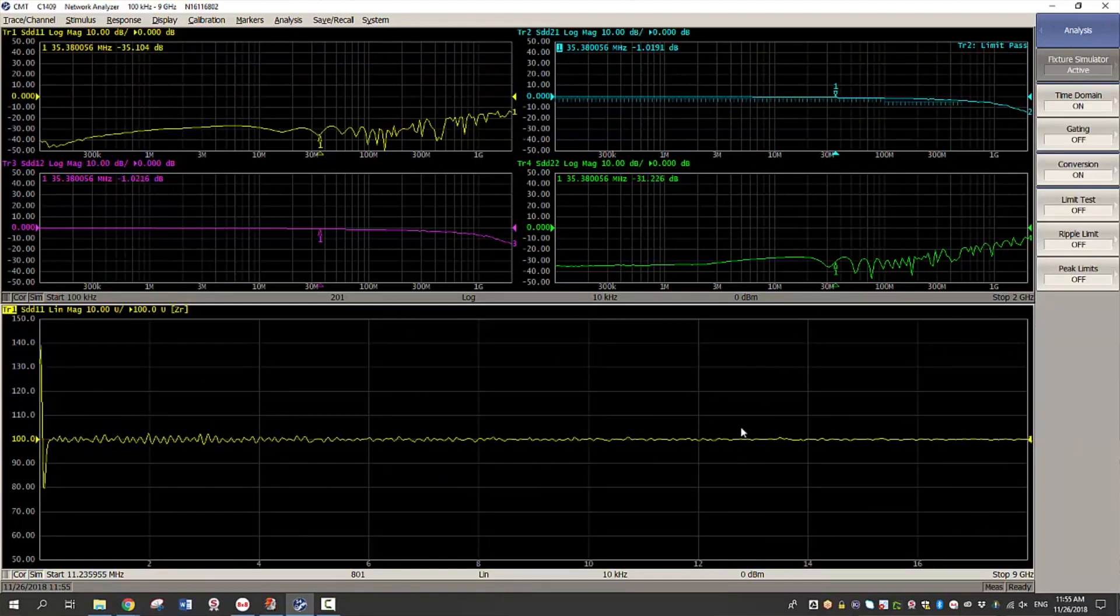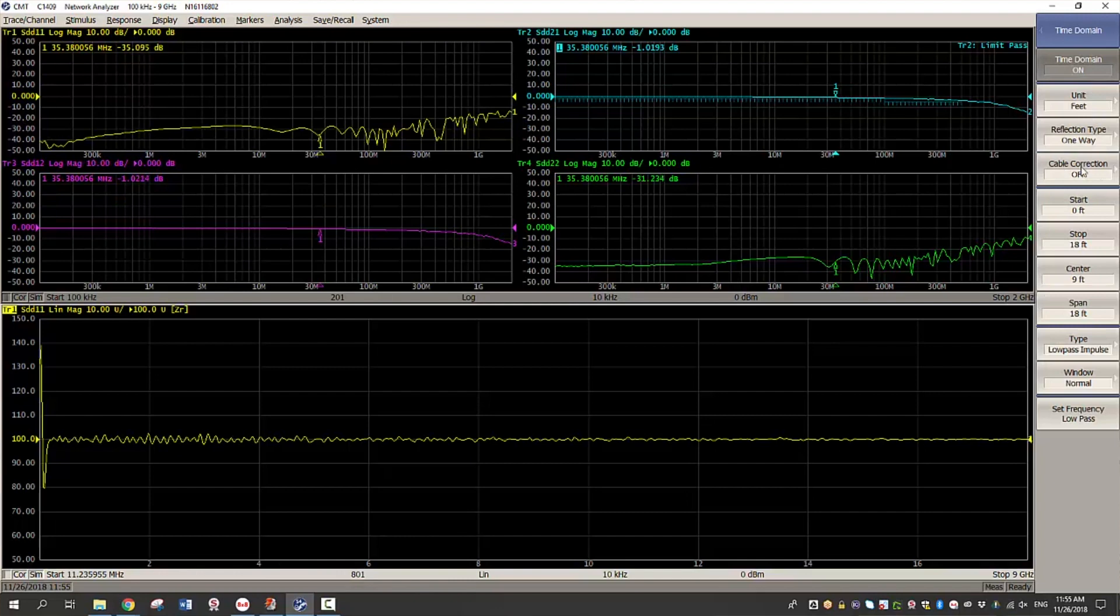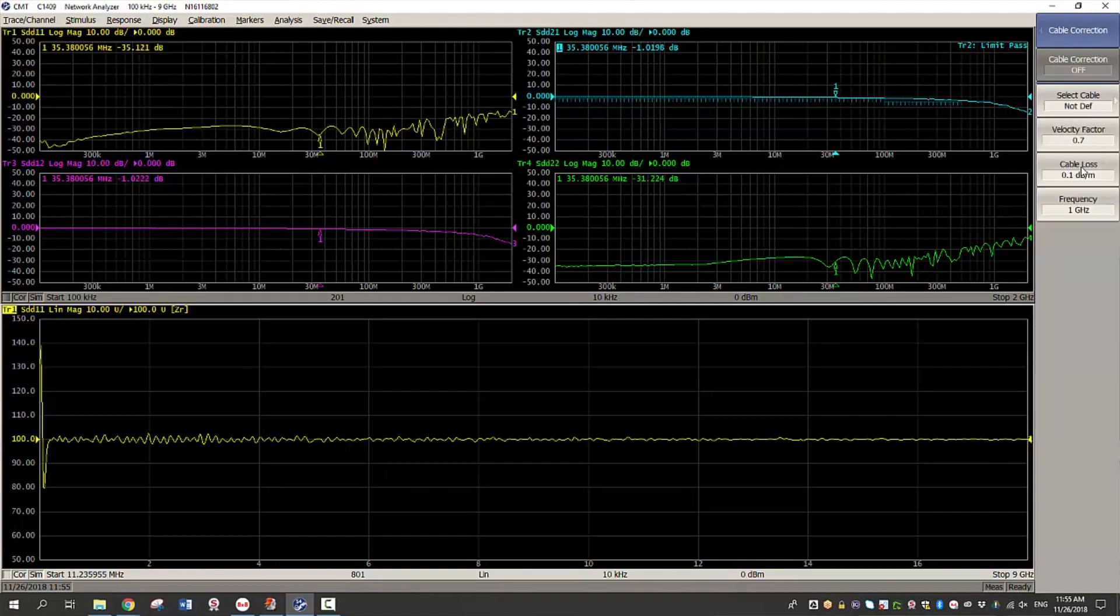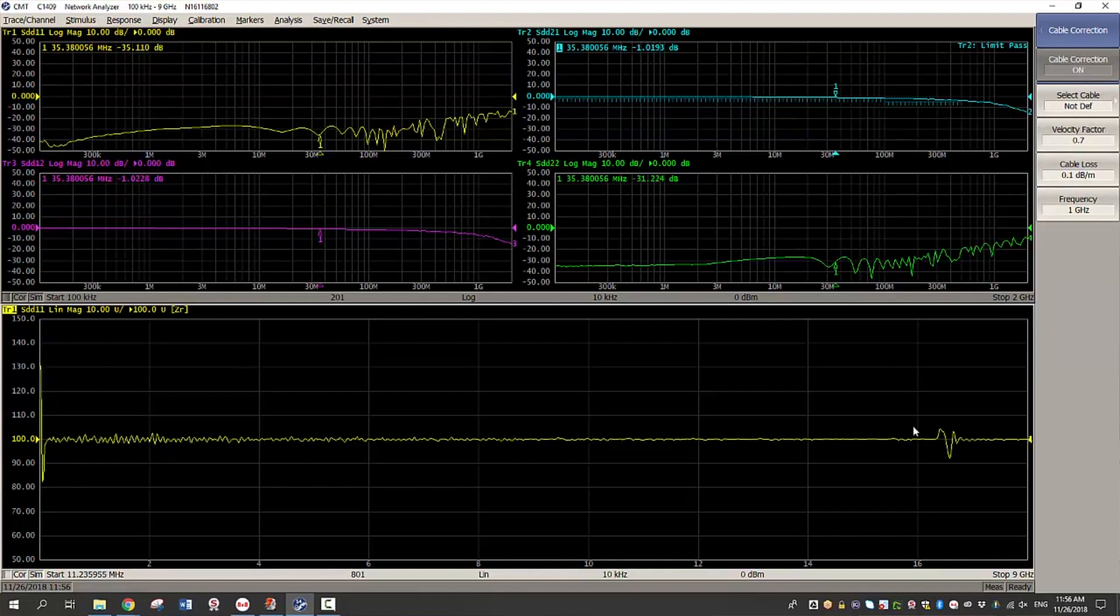So once you have turned on time domain, you will see impedance along y axis and then distance along x axis. In order to identify the exact fault location, you must enter the correct velocity factor as well as the cable loss. So once you have entered them, you will see the exact mismatch locations.